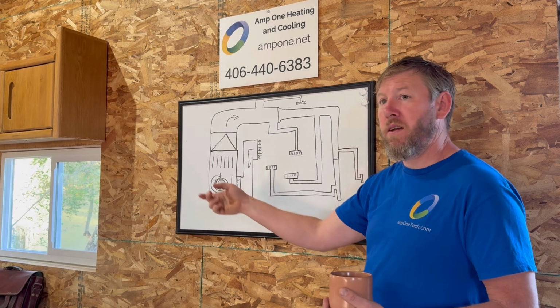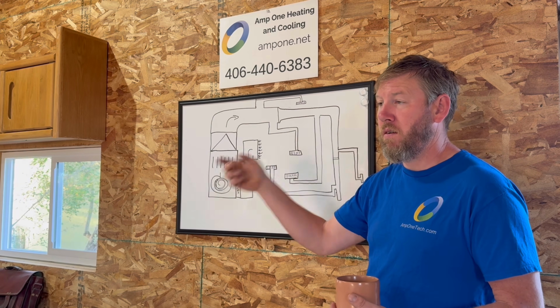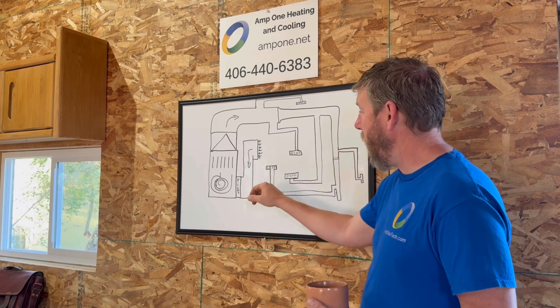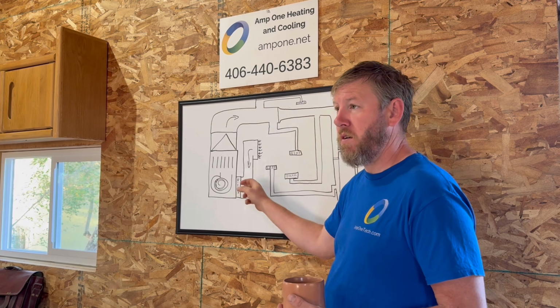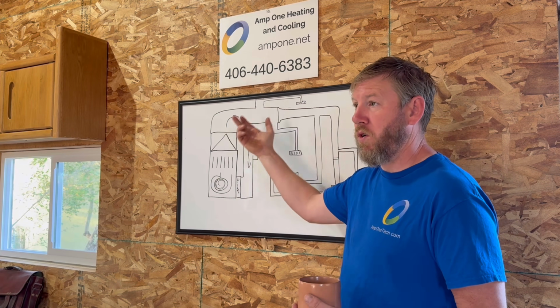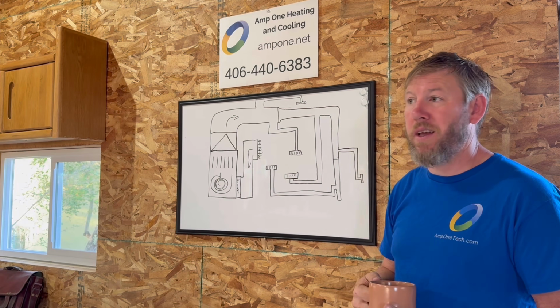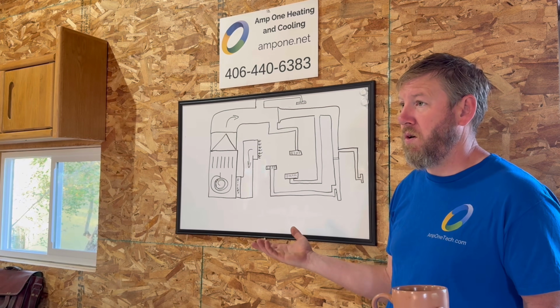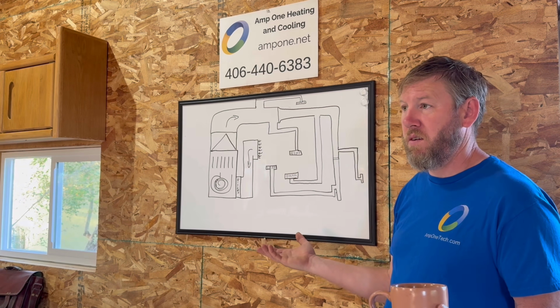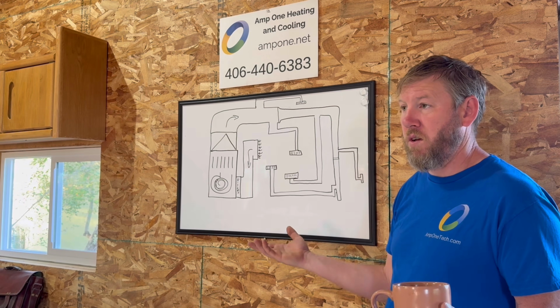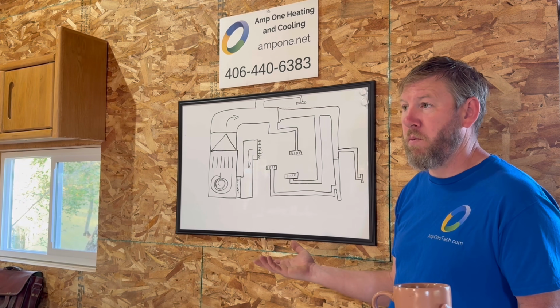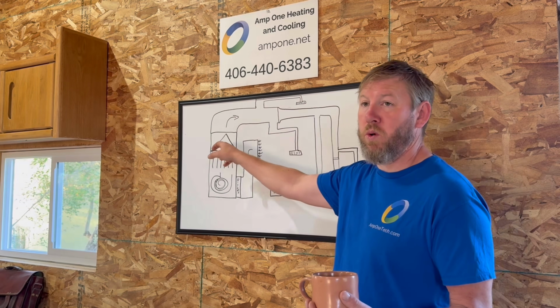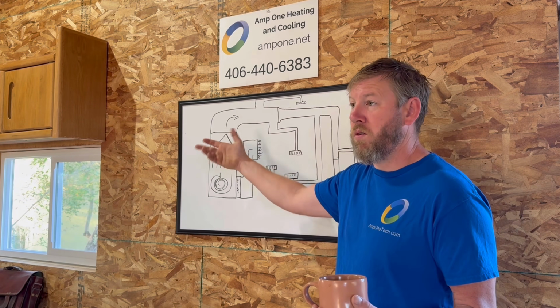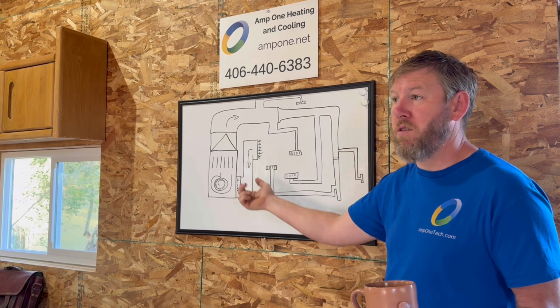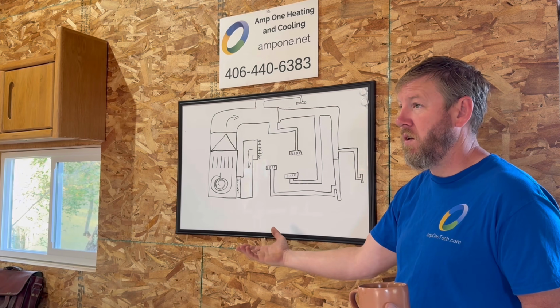A lot of times if it's picking up too much heat, we're looking at airflow issues, and that is kind of what we're getting into today. Airflow affects our superheat going back out. If your filter's dirty and you're slowing the airflow across that coil, it's not picking up as much heat. So what is that going to do to your superheat? It's going to drop it down. That coil's going to get colder, and when the coil gets colder, it'll freeze up. That's why we get freeze ups when the filter's dirty.